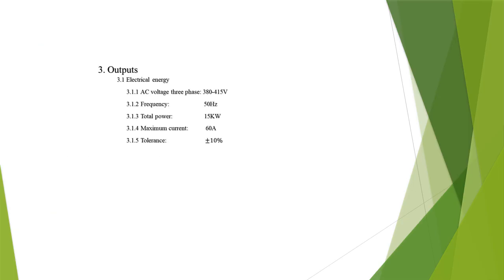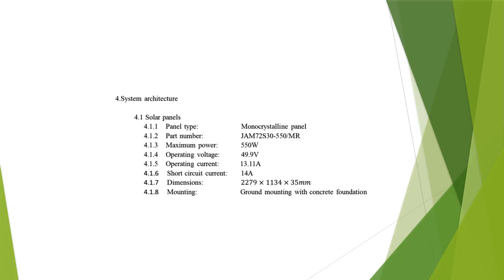So we move to outputs from the system. From the system, we get electrical energy, which is AC voltage, 3-phase, 380 to 415 volts at 50 hertz frequency. And total power should be 15 kilowatt and maximum current of 60 amps. And the tolerance will be plus or minus 10%. So we move on to system architecture.